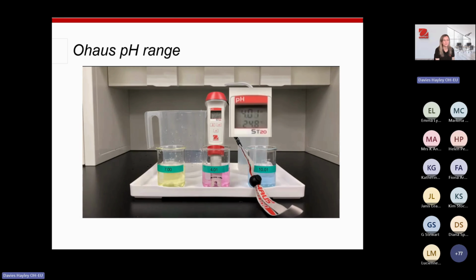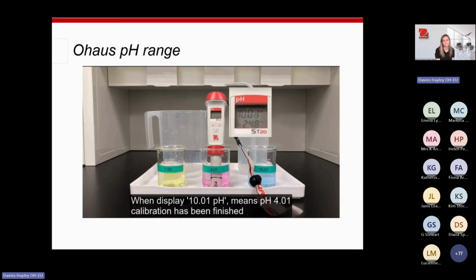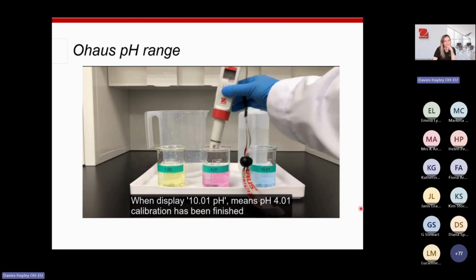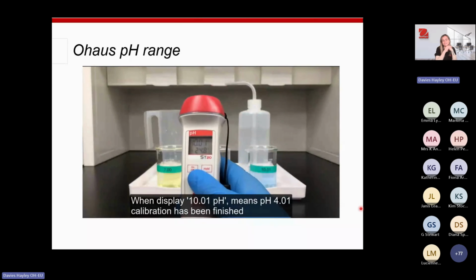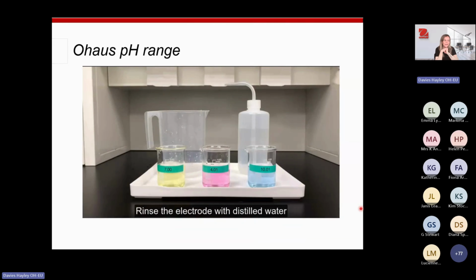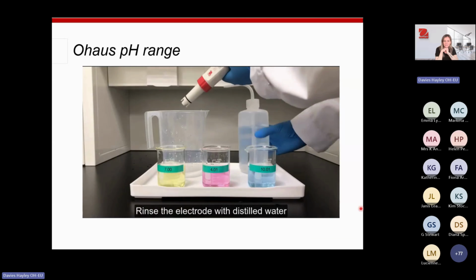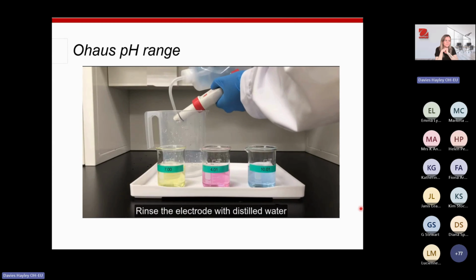is it will flash up 10.01 once it's calibrated, and then you will just repeat, rinse the electrode, dab it dry, and pop it in the pH 10. So I'll leave that running in the background. So that's essentially how quick and how easy the ST20s are to calibrate.